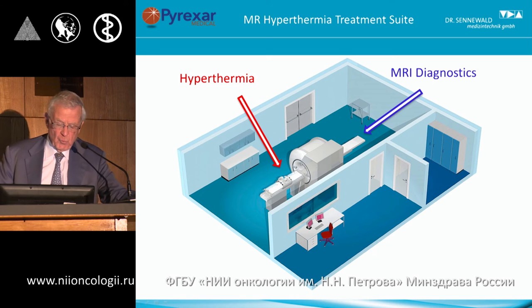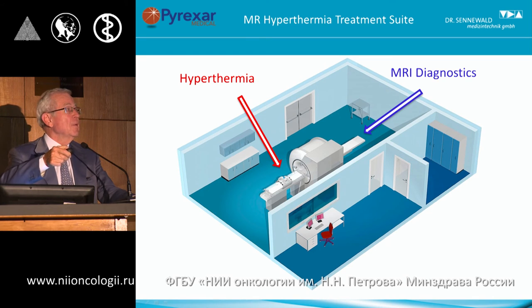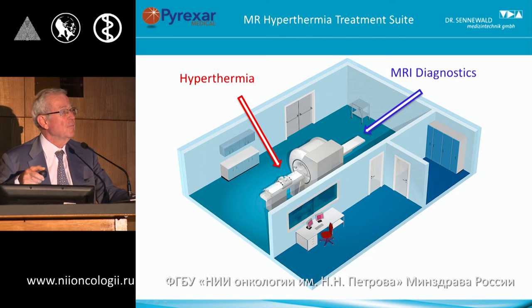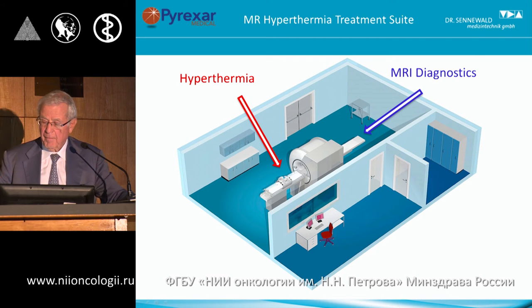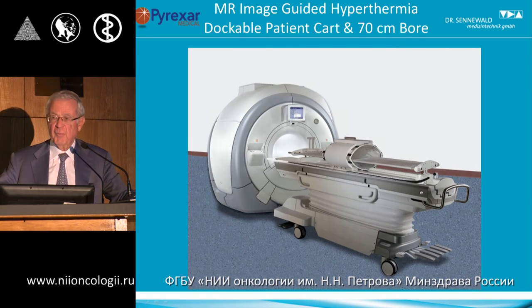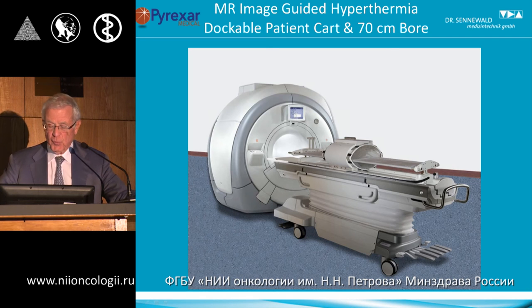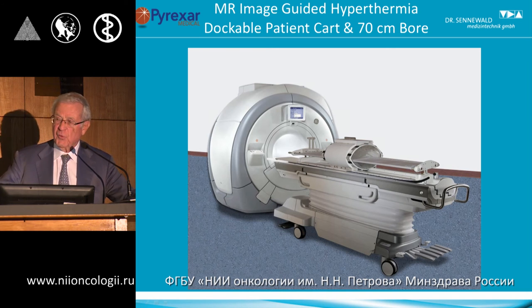This is a typical treatment suite as we have used it so far: a shielded room not much different from any MRI room, an operator room, and a technical room. In these early systems, the treatment side was on one side of the magnet and the diagnostic side on the other. Our newer devices, as with the General Electric adaptation, are conceived differently — both diagnostic and therapeutic use are arranged on a dockable cart, with one cart for therapeutic hyperthermia use and another for diagnostic use.